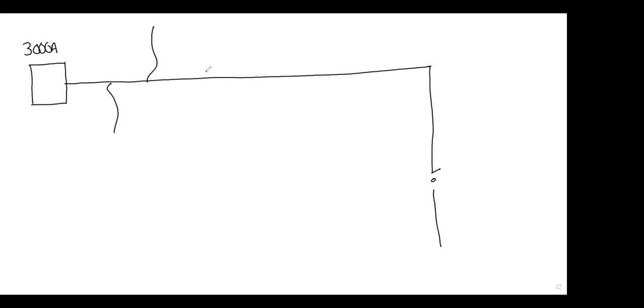Tap lines, fuses, transformers, all this kind of stuff, right? The breaker is open. Is there load on this circuit? Can y'all hear me? If the breaker's open, there is no load. Anybody else? Yeah, there is load. There's tons of load out there. It's not energized, but there's a lot of load out there. Okay, it's not energized yet.